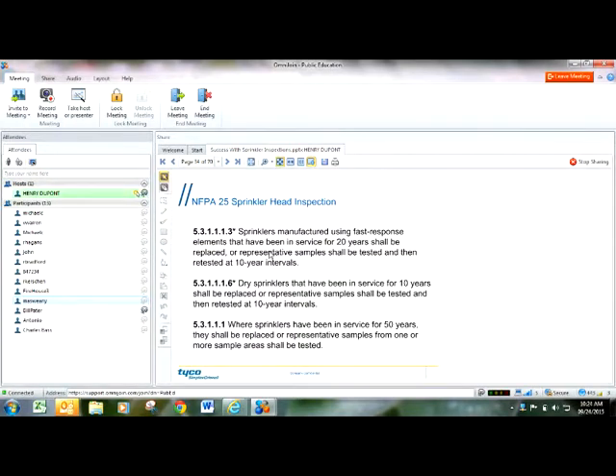This is kind of a newer one. Quick response sprinkler heads that have been in service for 20 years shall be replaced or tested. Dry pendant sprinkler heads, we talked about those a few slides ago. If they've been in service for 10 years, they have to be replaced or tested, and then tested every 10 years after. Where your standard, regular, run-of-the-mill wet pipe sprinkler systems are found, if the heads are 50 years old, they've got to be replaced or tested.